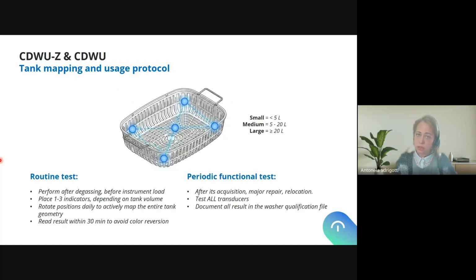When we change the solution, we put in the water first, treated water ideally, to preserve my instruments and the metallic parts of my ultrasonic washer, and also the detergent at the right dose. We wait for the temperature to be reached, and then we perform the degasification. As I have mentioned, this is mandatory. After degasification, we put in a number of indicators depending on the size of the machine, and only after we have corroborated that the ultrasonic washer is working correctly will we load our instruments. So it's change of solution, degasification, testing, load.